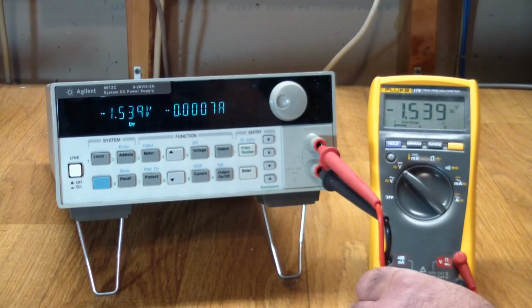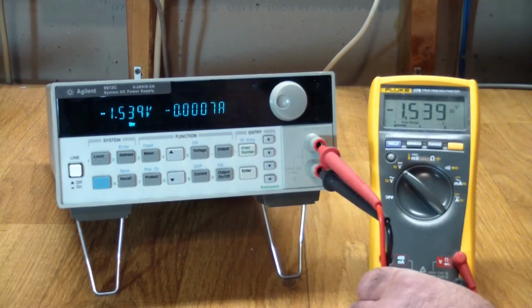So another thing to note is that the unregulated annunciator light is on, and that's basically telling us that the device is saying, I'm trying, but I cannot give you what you've programmed into me. So there's the problem. Could be one of many things, but let's take the device apart and have a look at the service manual, which is still available from the Agilent website.